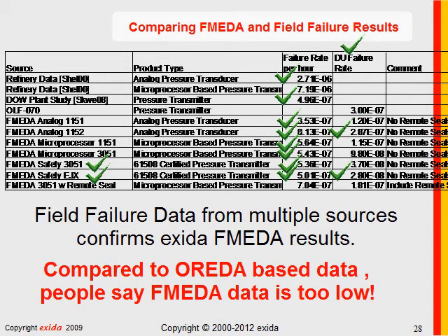When scanning failure rate data from many different sources, most are in the correct range from an FMEDA. There are some, like the OREDA database, where the OREDA failure rates are much higher than FMEDA data. We do need to sort through that and find out exactly why. But right now, just remember that OREDA data says FMEDA is too low.